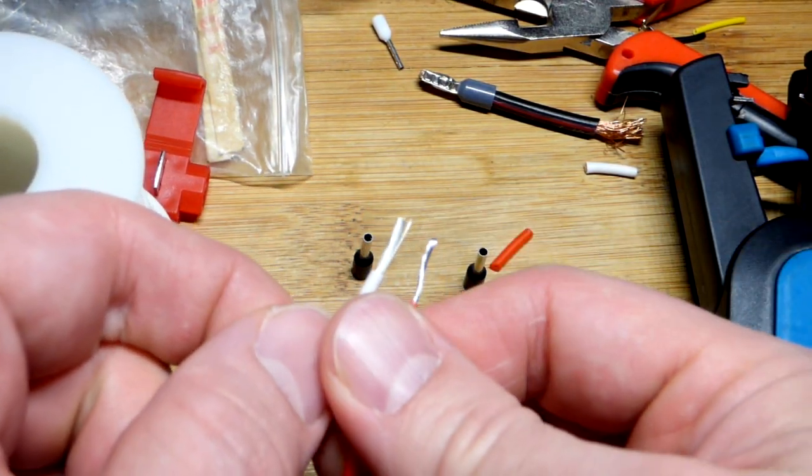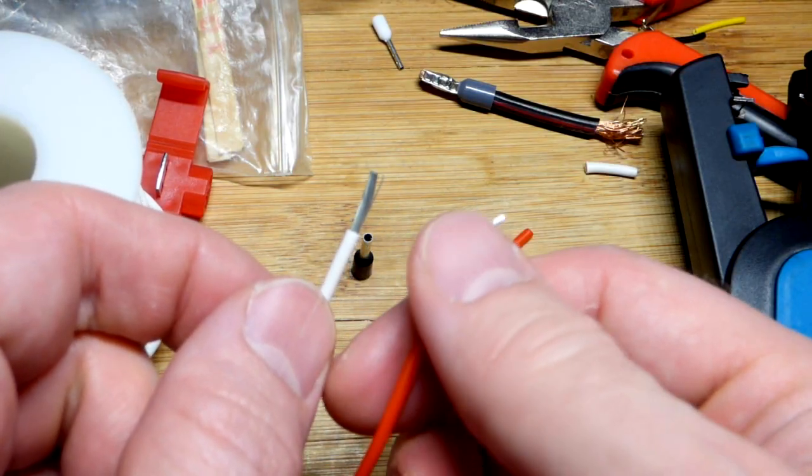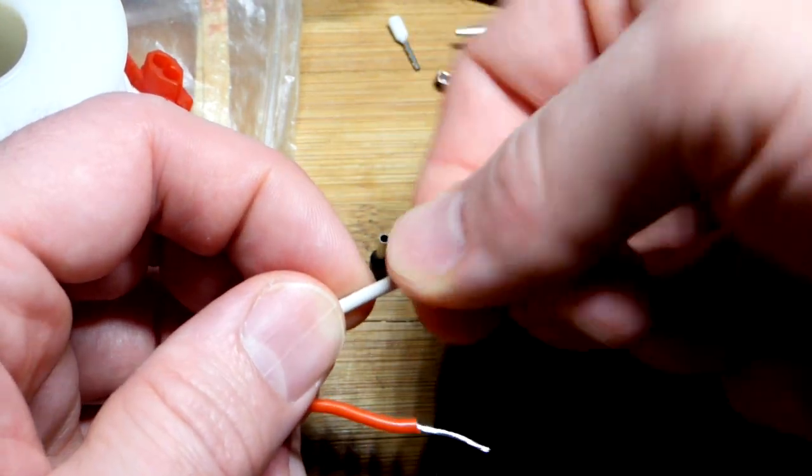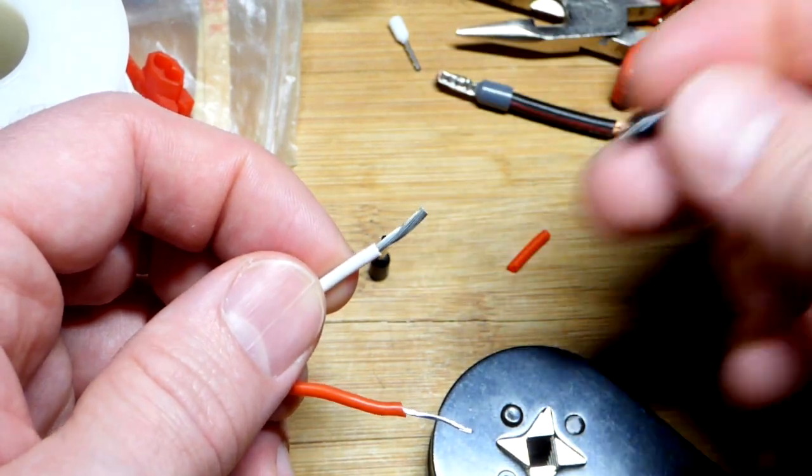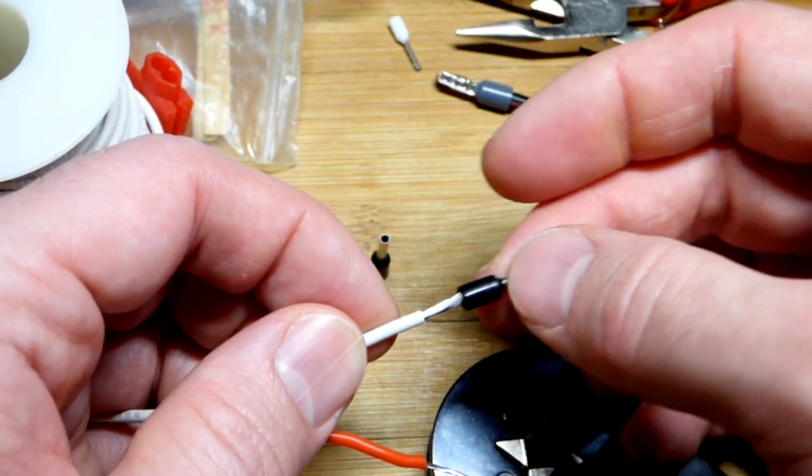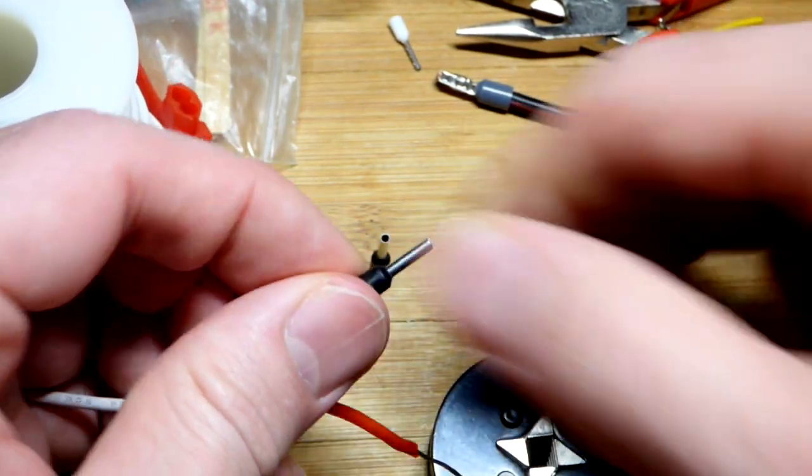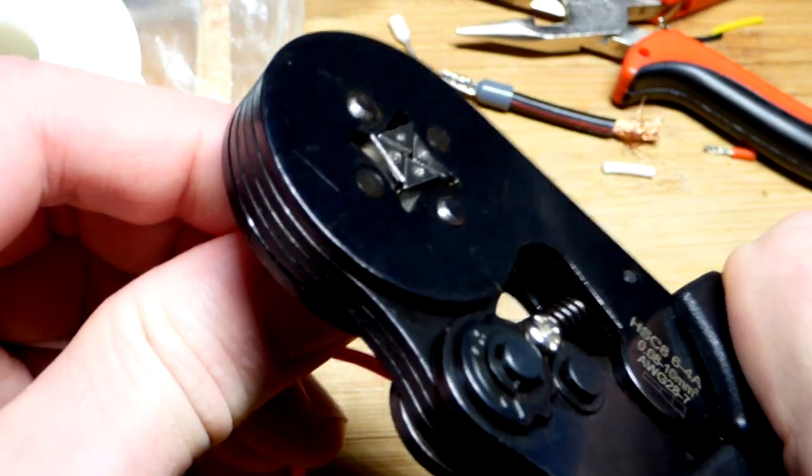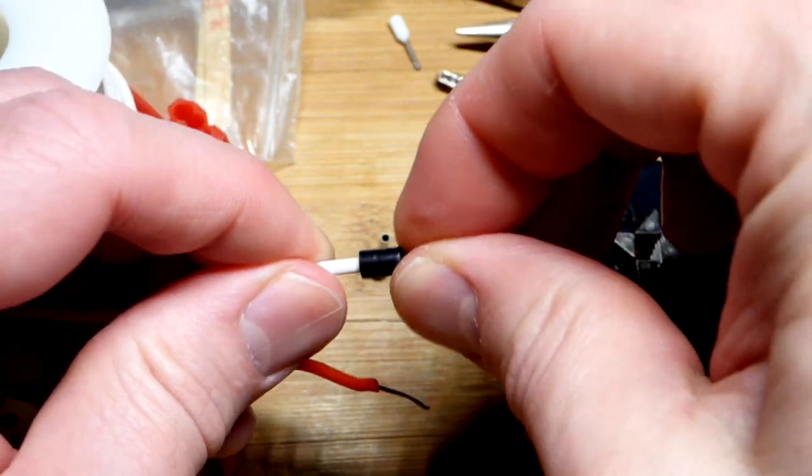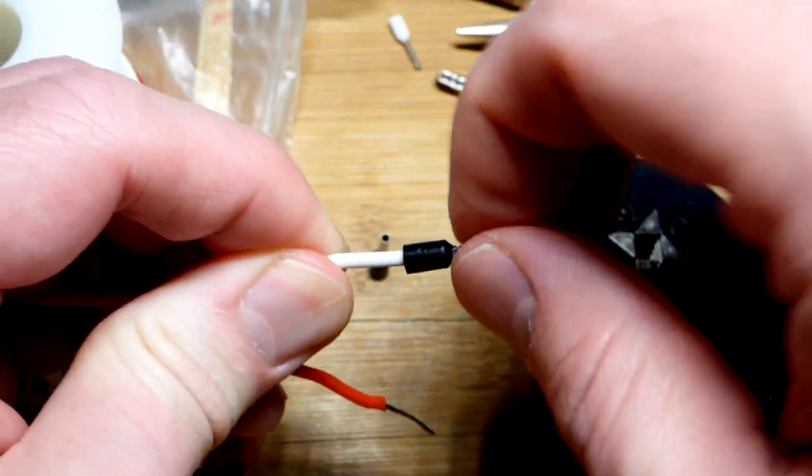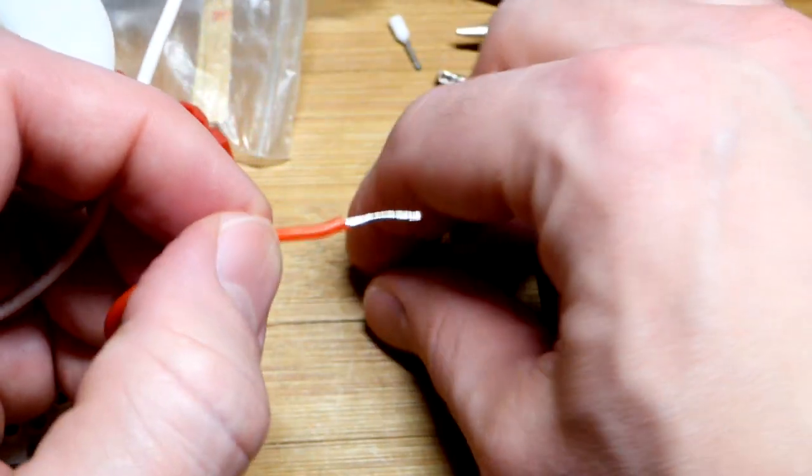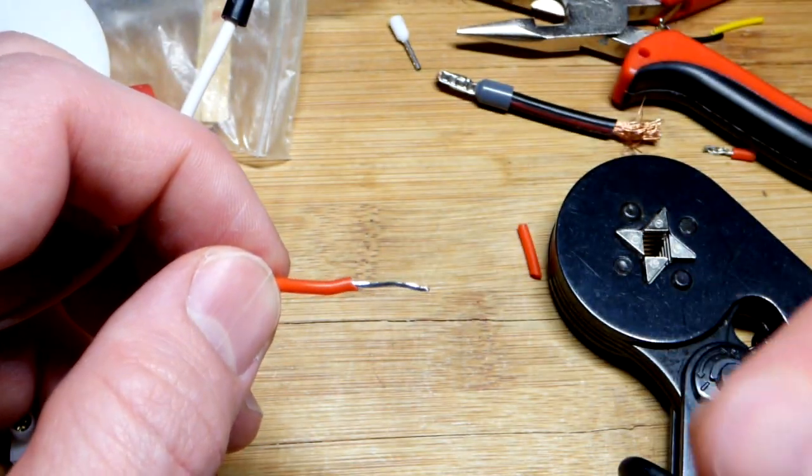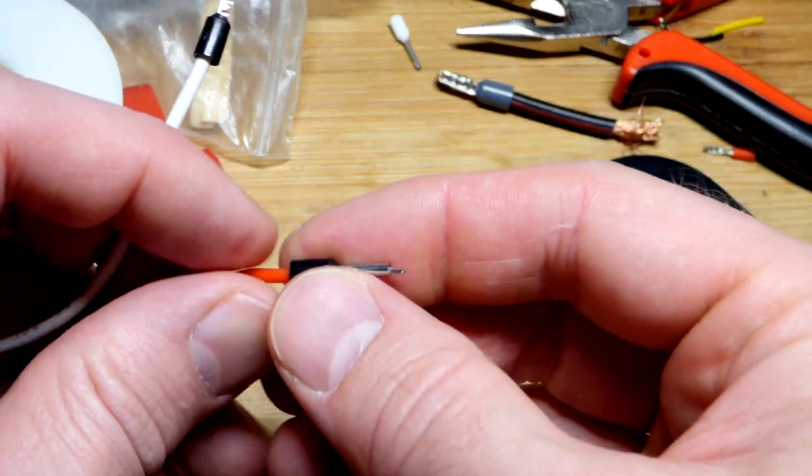It's kind of hard to tell if that's as large as my 16 gauge right there. This is tinned so it's kind of soldered together and maybe that's just bunching them up better. Now I'm pretty sure I crimped ferrule to this 16 wire gauge a lot of times. You just give a slight twist just to kind of keep the strands together and slide this on. You're not trying to twist them up, just get the strands together and then slide it in the crimping tool. It's auto adjusting. You should be able to tug on it and it not pop off.